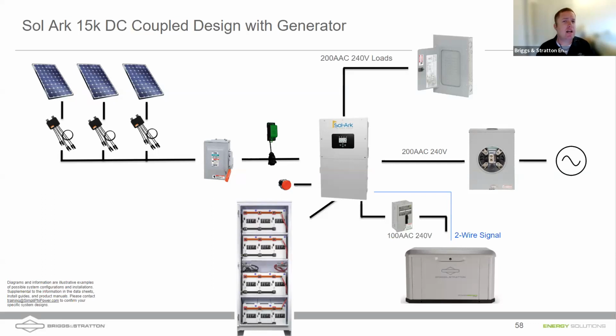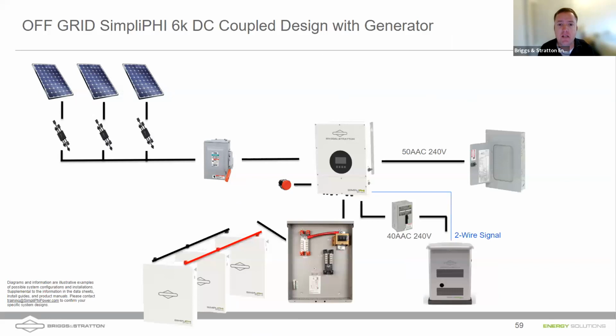The Sol Ark doesn't have the AP Smart Rapid Shutdown Transmitter built in. So in this example, I'm showing you the Tigo. Now, you could still use a Tigo on ours. You just have to buy the external rapid shutdown transmitter, which is that little green device you see just to the left of the Sol Ark. And then additionally, on each of the solar modules, you have the rapid shutdown devices. I think those are TS4Fs, but Tigo does make some optimizers as well, which is really exciting to work on.